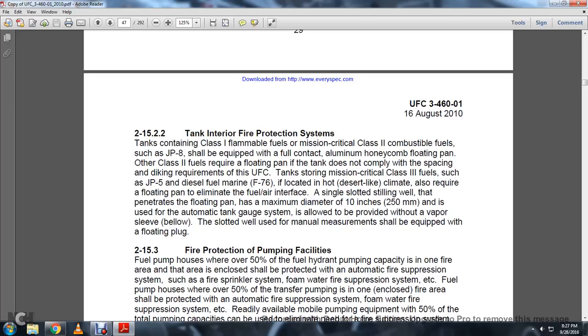215.2.2 Tank Interior Fire Protection System. Tanks containing Class 1 flammable fuels and mission critical Class 2 combustible fuels such as JP8 shall be equipped with a full contact aluminum honeycomb floating pan. Other Class 2 fuels require a floating pan if the storage does not comply with the spacing and diking requirements of the UFC. The tanks storing mission critical Class 3 fuels such as JP5 and diesel fuel marine F76, if located in a hot desert-like climate, are also required to have a floating pan to eliminate the fuel air interface.